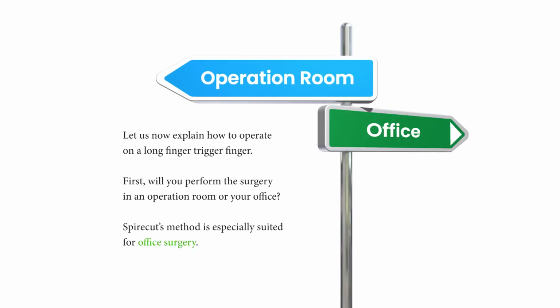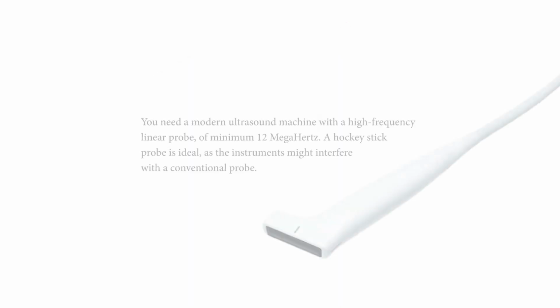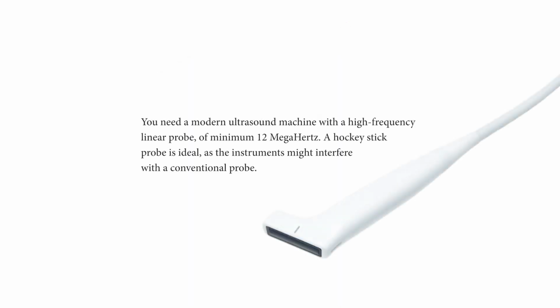First, will you perform the surgery in an operation room or your office? SpireCut's method is especially suited for office surgery. You need a modern ultrasound machine with a high-frequency linear probe of minimum 12 MHz. A hockey stick probe is ideal, as the instruments might interfere with a conventional probe.